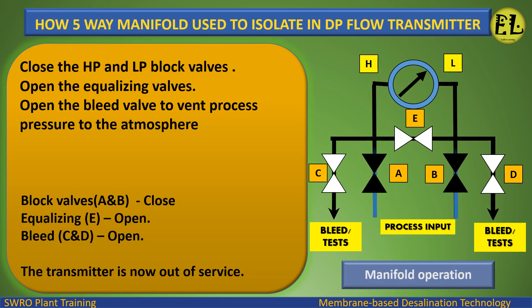How a five-way manifold is used to isolate in a DP flow transmitter: close the HP and LP block valves, open the equalizing valve, then open the bleed valve to vent process pressure to the atmosphere. Block valves A and B: close. Equalizing valve E: open. Bleed valves C and D: open. The transmitter is now out of service.